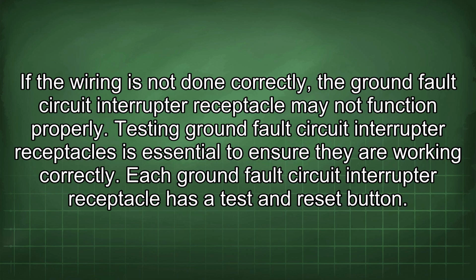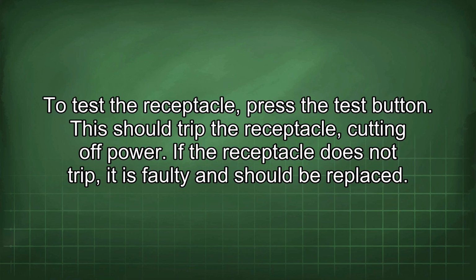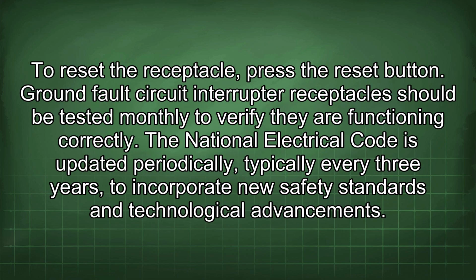properly. Testing ground fault circuit interrupter receptacles is essential to ensure they are working correctly. Each ground fault circuit interrupter receptacle has a test and reset button. To test the receptacle, press the test button. This should trip the receptacle, cutting off power. If the receptacle does not trip, it is faulty and should be replaced. To reset the receptacle, press the reset button. Ground fault circuit interrupter receptacles should be tested monthly to verify they are functioning correctly.